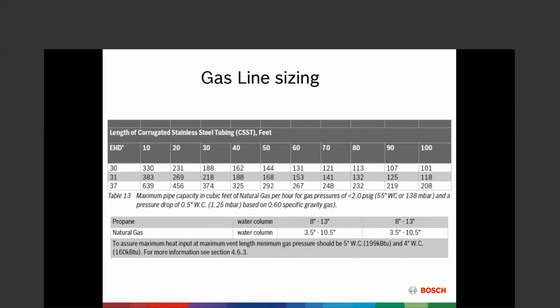We're also approved for convenience on CSST. It's great stuff. Some guys love it, some guys hate it, but when you're using that CSST, the corrugated stainless steel, make sure that you're observing the manufacturer's equivalent hydraulic diameter, so that it compares, or basically normalizes, it more or less to what black iron pipe would do. So that's what we want to use. Gas pressures that we're going to look at: propane 8 to 13 inches, natural gas 3.5 to 10.5. That's what we want to see gas pressure wise.